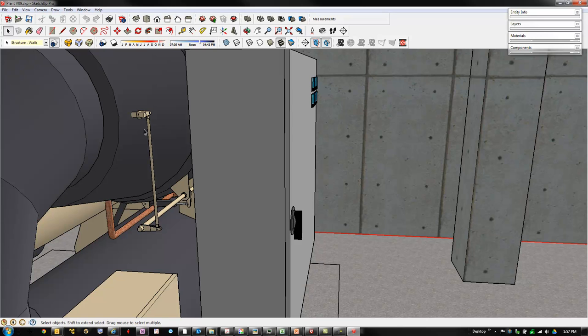Most centrifugal machines, if they're really well tuned up and properly adjusted, the inlet vanes can probably unload them to 20-25% of their rated capacity. But if you try to further unload them with the inlet vanes, a phenomenon called surge happens. Basically, the refrigerant's trying to exit the impeller faster than it can get into the eye of the impeller, so the pressure causes the refrigerant that left the impeller to reverse back through the impeller, and the machine makes a very loud and bad noise. It can sort of bounce around. It's not a good thing. You'll know it when it happens.